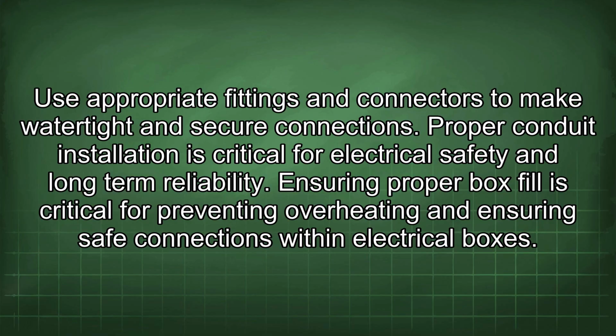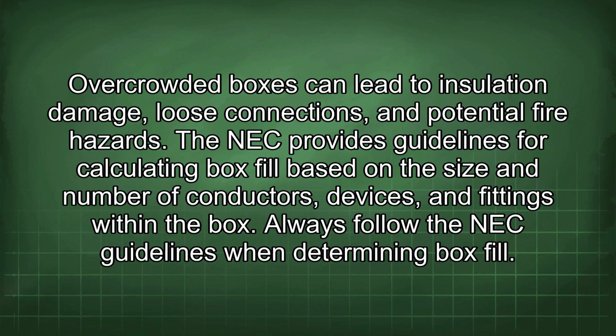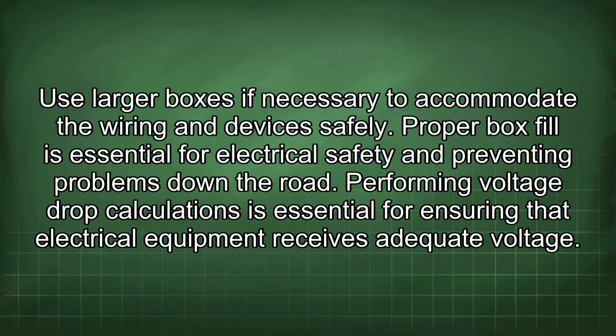Ensuring proper box fill is critical for preventing overheating and ensuring safe connections within electrical boxes. Overcrowded boxes can lead to insulation damage, loose connections, and potential fire hazards. The NEC provides guidelines for calculating box fill based on the size and number of conductors, devices, and fittings within the box. Always follow the NEC guidelines when determining box fill. Use larger boxes if necessary to accommodate the wiring and devices safely. Proper box fill is essential for electrical safety and preventing problems down the road.